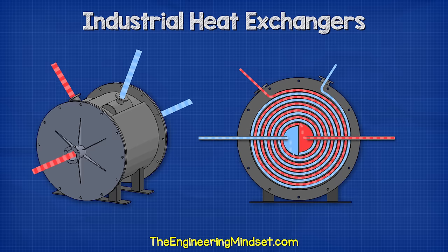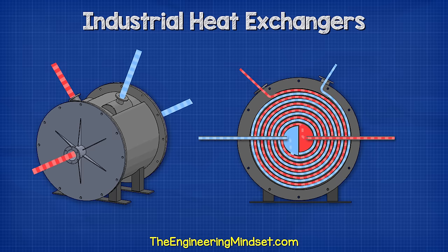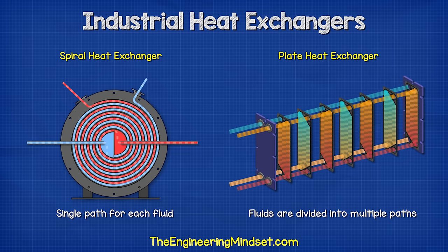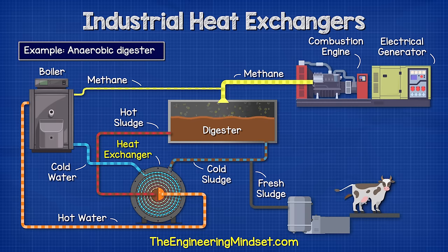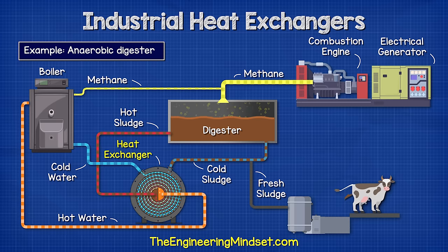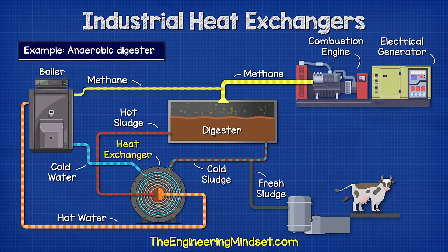This type of heat exchanger isn't as commonly used. However, because the design has only one channel for the fluid to flow through, the velocity remains high, making it harder for fouling to occur — whereas plate and tube heat exchangers divide the flow into multiple paths. So these are ideal for installations where sludge-like substances are processed. For example, in an anaerobic digester, the thick sludge is recirculated through a spiral heat exchanger to maintain a certain temperature, which releases methane from the digester to power an engine and turn an electrical generator.